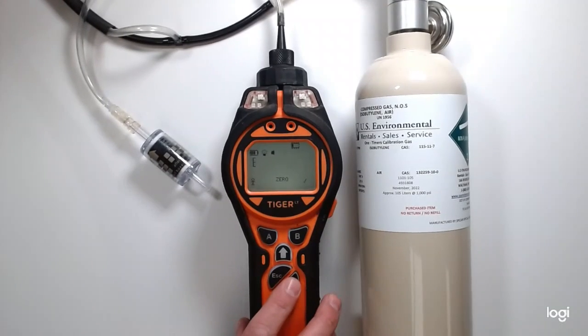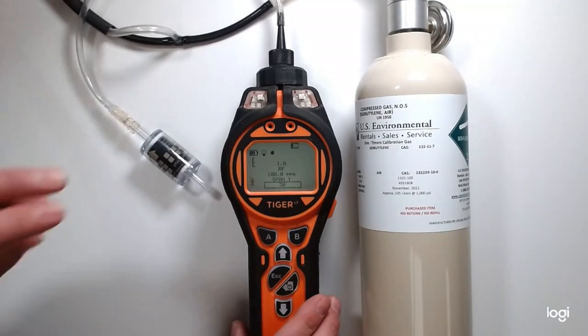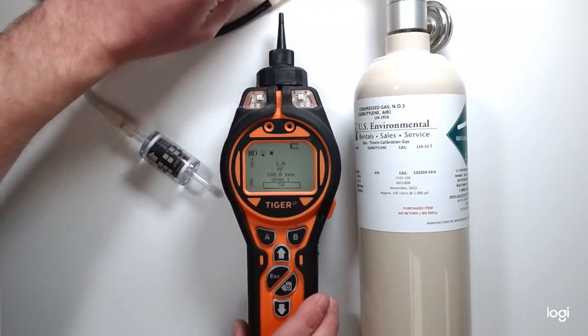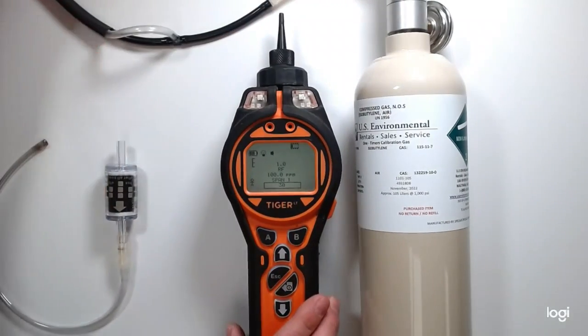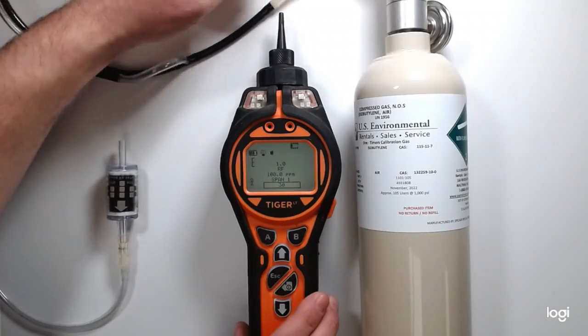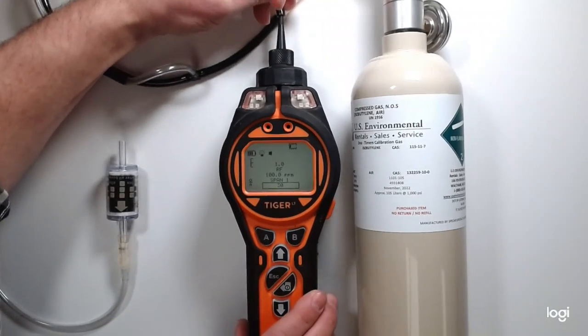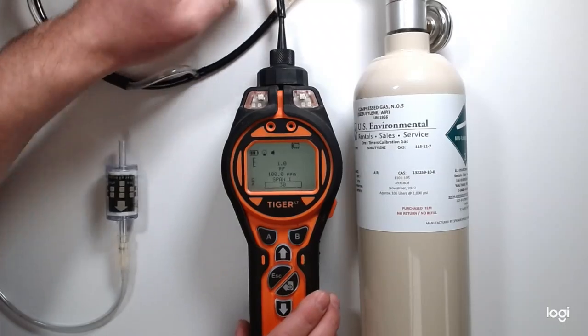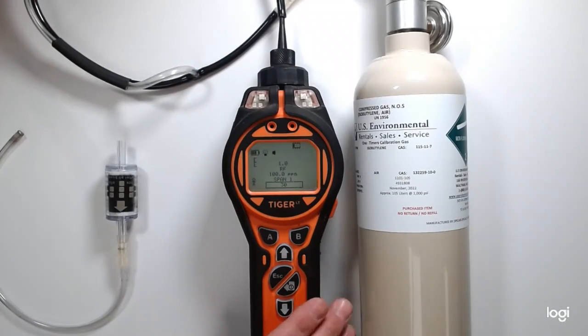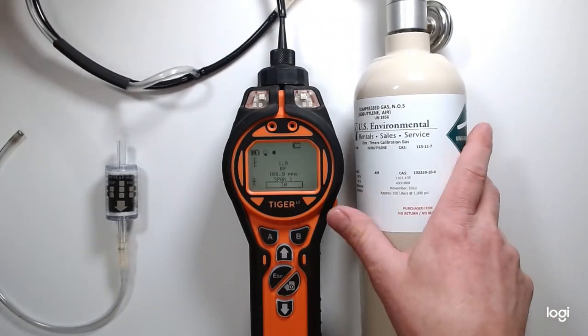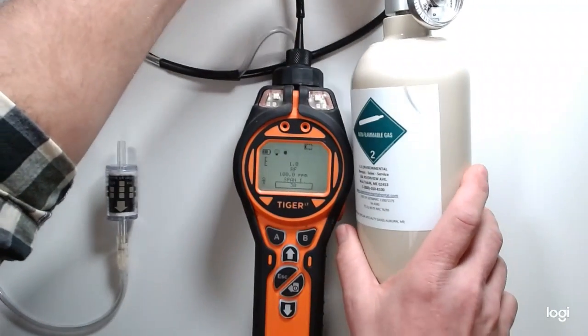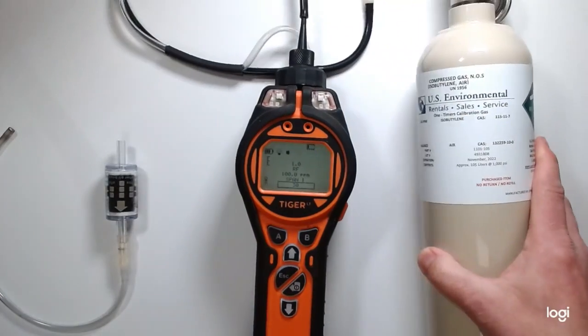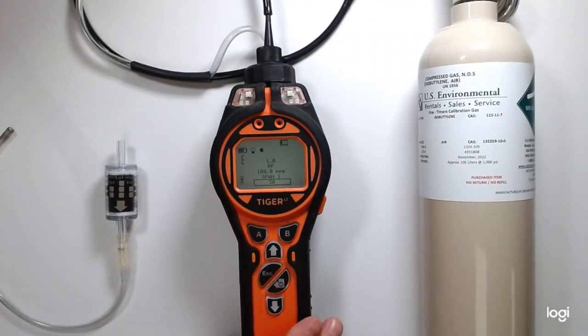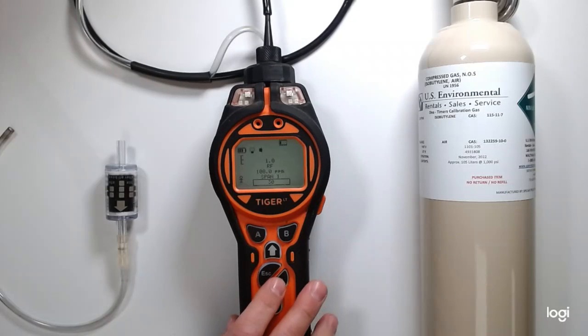Now that the unit is zeroed, I'll hit the enter button, and it will ask for the span. We'll remove the zero filter. We're using a T as opposed to a Tedlar bag in our video, which will just bleed off the excess. We'll attach our hose, and we'll adjust our regulator to 1 liter per minute. Once we have the gas flowing, we'll hit the enter button, and it will count down from 30.